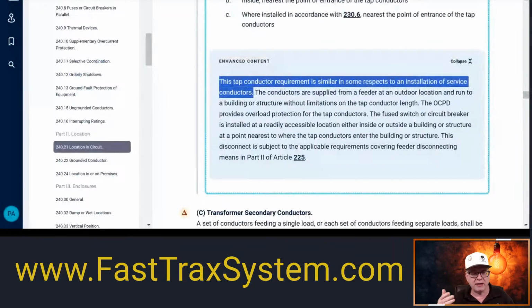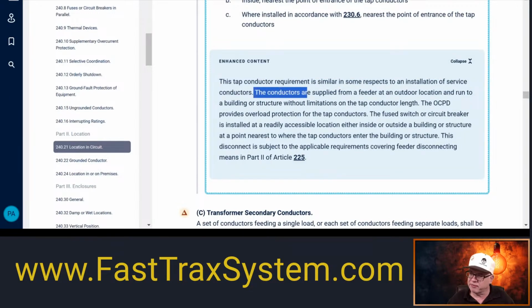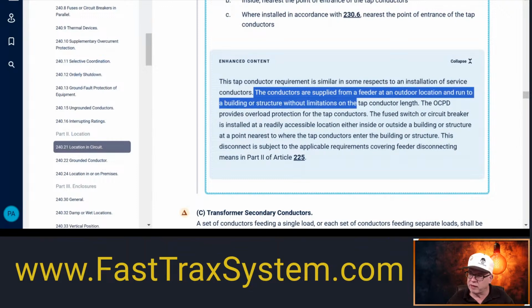You remember we talked about it, dealing with 230.70(A)(1). It says the conductors are supplied from a feeder at an outdoor location and run to a building or structure without limitations on the tap conductor's length. No length. The only other limitation that I can tell you we would have, because remember, this is all outside. So you tapped a feeder outside and you're running it to a certain location outside. There's no length limitation. There's no 10-foot tap rule. There's no 25-foot tap. It's unlimited.